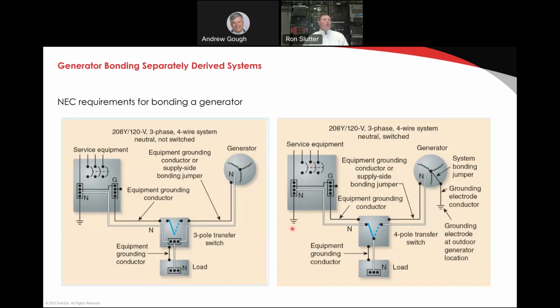So if you were to use a typical system, and 99% of the systems you have are this, the generator is solidly grounded to the ATS and the main service. So there's one neutral to ground bond right here. Okay, and that's pretty much how most should be.